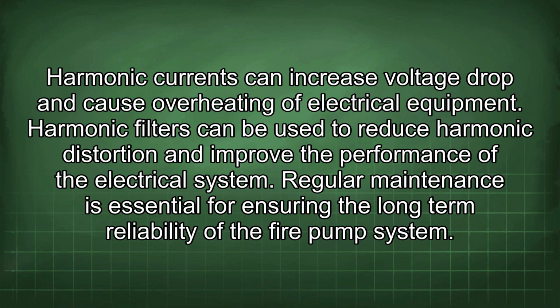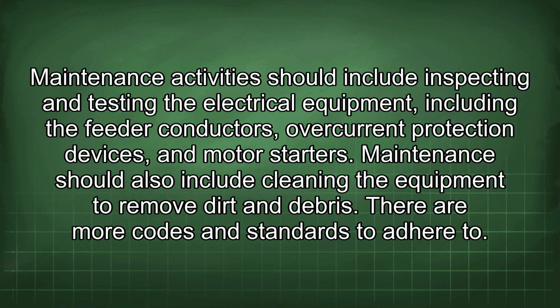Regular maintenance is essential for ensuring the long-term reliability of the fire pump system. Maintenance activities should include inspecting and testing the electrical equipment, including the feeder conductors, overcurrent protection devices, and motor starters. Maintenance should also include cleaning the equipment to remove dirt and debris. There are more codes and standards to adhere to.